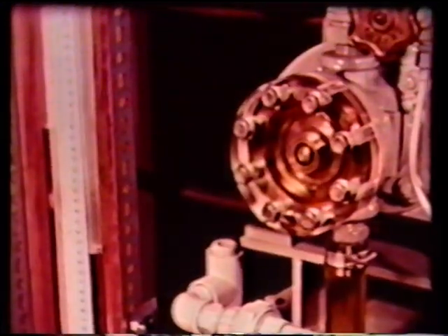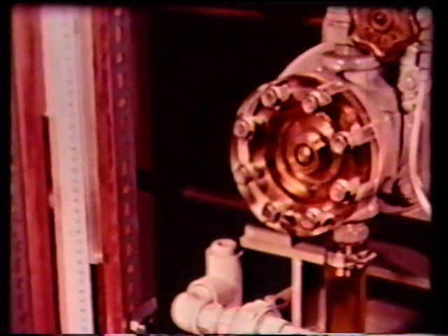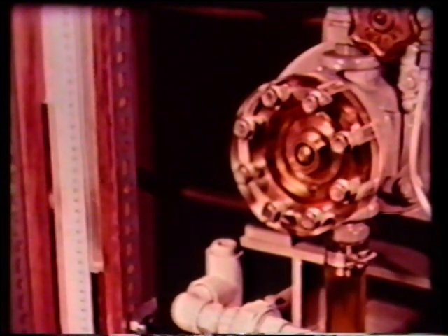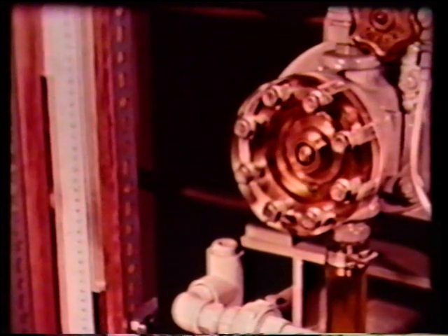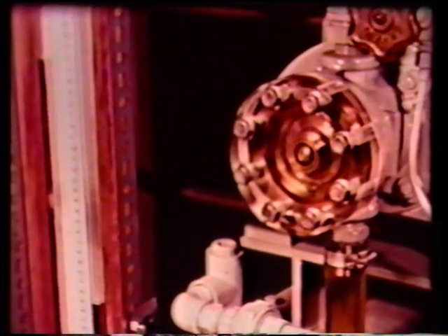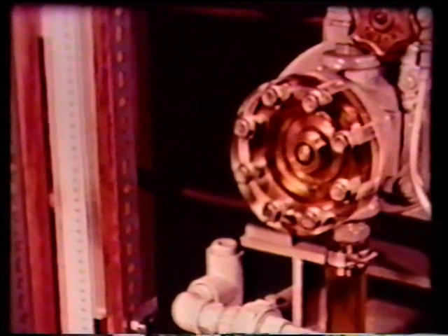In order to induce vapor cavities in the fluid, the pump inlet is restricted with a gate valve in the fluid sump. As the valve is closed, a negative pressure shows on the manometer connected to the pump inlet. Soon a point is reached where vapor cavities can be seen entering the pump through the transparent inlet pipe.